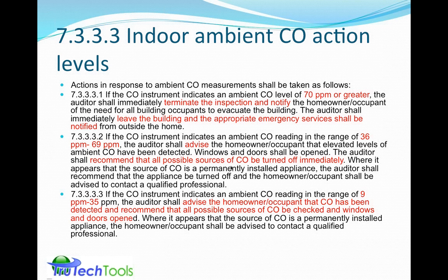Then in the range of 9 to 35, you give advice that CO has been detected, and recommend that CO be checked and windows and doors be opened. So you're giving a recommendation that things are not looking correct when it's above 9 parts per million. So it's 9 to 35, 36 to 69, and then 70 and above.